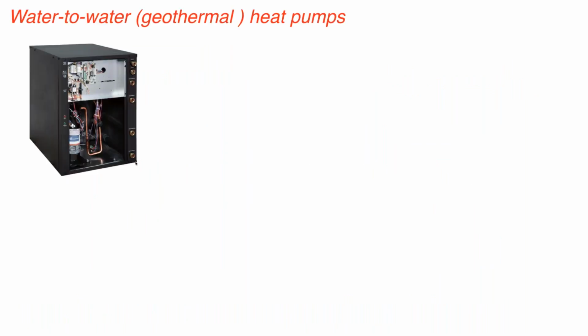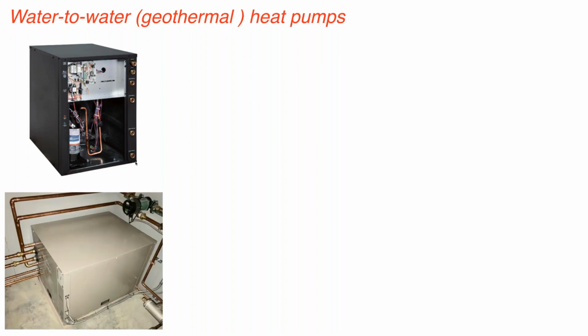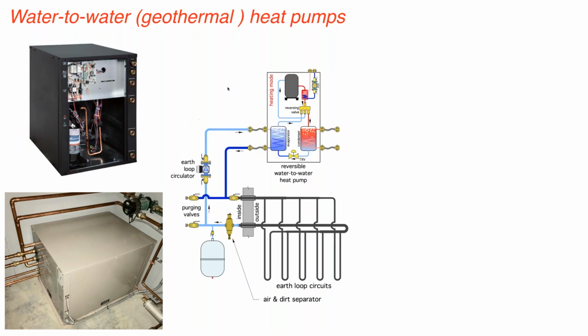Again, water to water: several manufacturers have water-to-water units that would be suitable for residential, like commercial applications. This is a nominal 4-ton unit installed. You can see the piping there on the left. The two smaller pipes at the bottom actually go to a domestic water tank. It's a de-superheater. That would be these two pipes right here. So when this unit is operating in cooling, some of the heat coming off the hot refrigerant coming off the compressor actually heats domestic hot water. So under those conditions, you're getting free heat recovery.